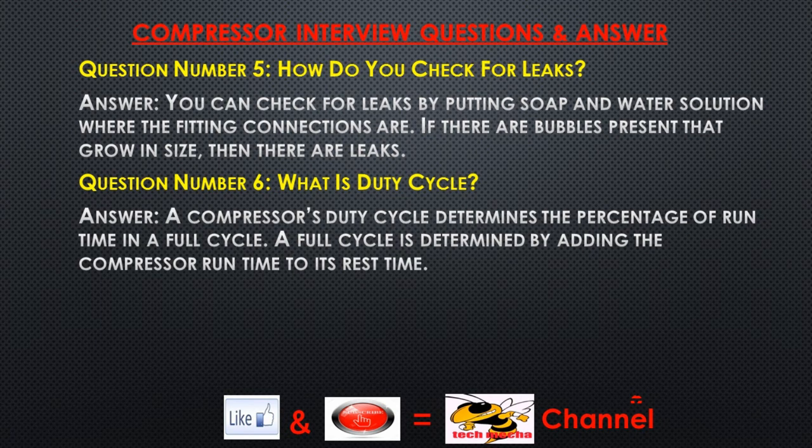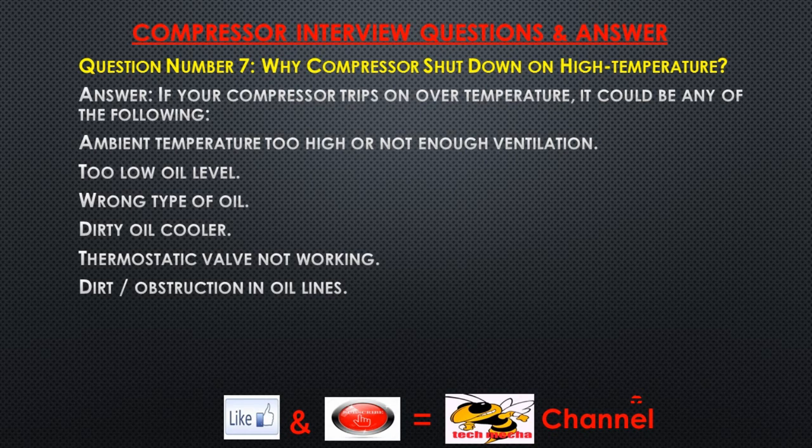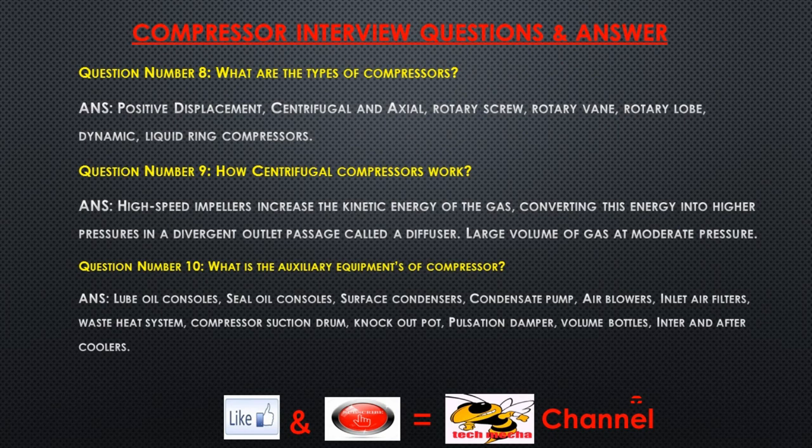Question number 7: Why do compressors shut down on high temperature? Answer: If your compressor trips on over temperature, it could be any of the following: ambient temperature too high or not enough ventilation, too low oil level, wrong type of oil, dirty oil cooler, thermostatic valve not working, or dirt obstruction in oil lines.